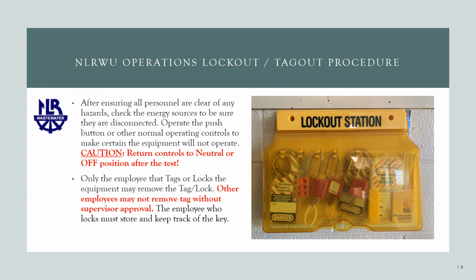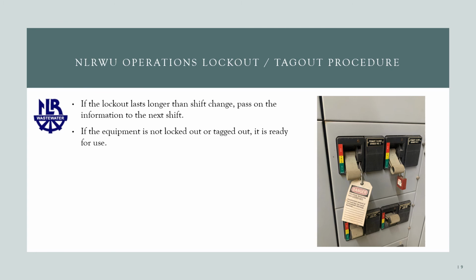After ensuring all personnel are clear of any hazards, check the energy sources to be sure they are disconnected. Operate the push button or other normal operating controls to make sure the equipment will not operate. Return the controls to neutral or off after you've tested it. Only the employee that tags or locks the equipment may remove the tag or lock. Other employees may not remove the tag without supervisor approval. The employee who locks must store and keep track of the key. If the lockout lasts longer than a shift change, pass on the information to the next shift. If the equipment is not locked or tagged out, it's considered ready for use.